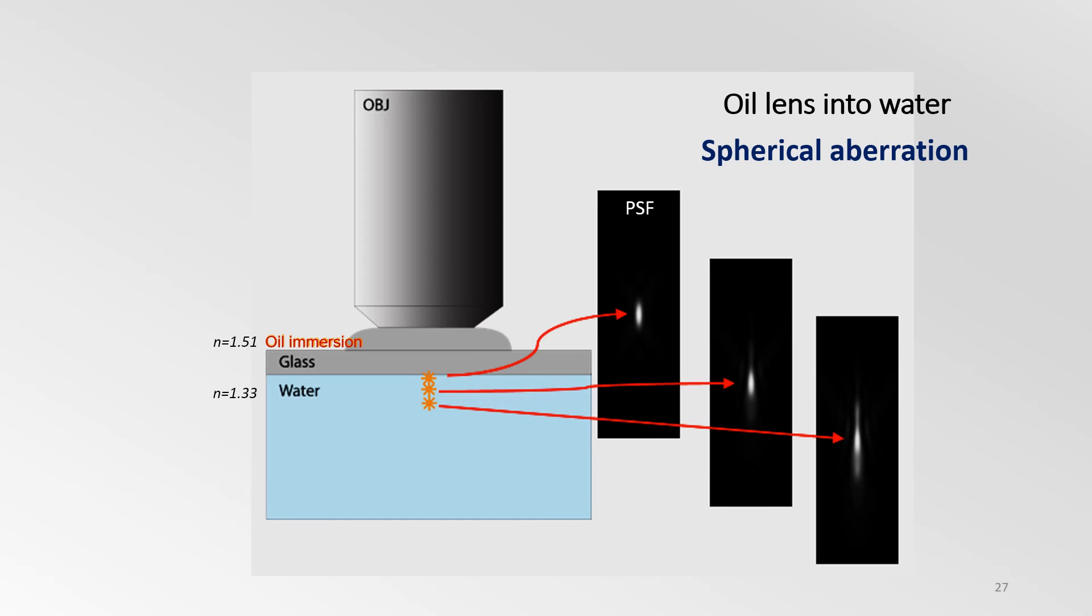For instance, if an oil immersion lens is used to image a sample immersed in an aqueous medium, the mismatch in refractive indices messes with the PSF as light goes deeper into the sample. This causes spherical aberration, bringing about the loss of information, resolution, and brightness with imaging depth and results in images that are far from optimal.